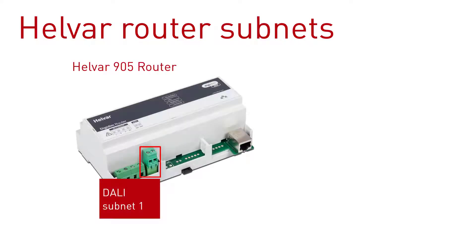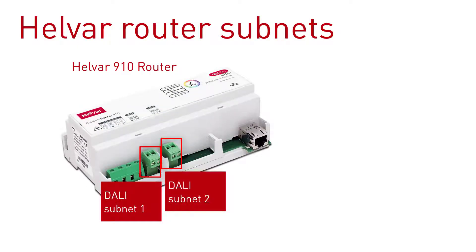The 905 has one DALI subnet. The 910 has two DALI subnets. And the 920 has two DALI subnets and also connects to SDIM and DMX. This means that you see different subnets when you're in Designer in Devices view, depending on what type of router is in the workgroup.